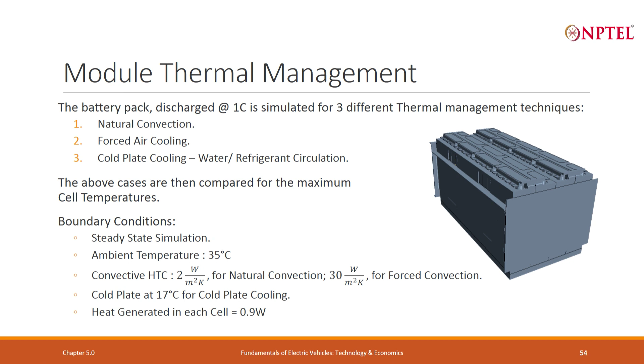We have done steady state simulation at ambient condition of 35 degrees. The heat transfer coefficient for natural convection is 2 watts per meter square per Kelvin, and for forced convection it is 30 watts per meter square per Kelvin. In the case of cold plate, we maintain the cold plate temperature at 17 degrees centigrade. Heat generation in each cell remains the same in all 3 cases, 0.9 watt.